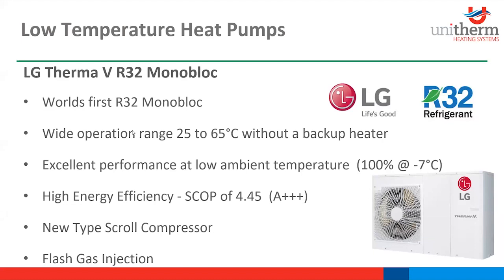So the flash gas injection. This is where I come back to the 65 degrees. In a normal thermodynamic cycle, your compressor can only get so much heat out before it overheats. With the LG Therma V and the flash gas injection, when it's compressing, halfway up its thermodynamic cycle, it gives it a wet vapor injection, and this cools the compressor so it can further compress and get higher pressure and higher temperatures out of the thermodynamic cycle.